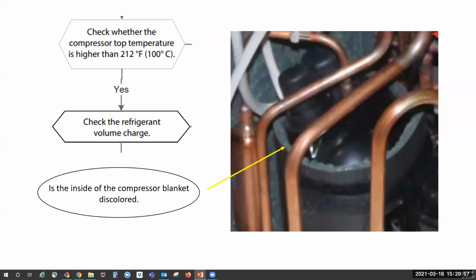Low refrigerant charge or restricted airflow can cause a P0, P6, or P4 code, and several different types of codes. Low refrigerant charge causes the compressor to overheat, and this is the main reason for compressor failures. Proper installation, good flares, and a good cut and deburring can prevent a refrigerant leak and save a compressor. There's only one way to verify that you have the correct charge inside the system, and that is to pull the refrigerant out and weigh it back in, charging according to the data plate, line set length and height if necessary.